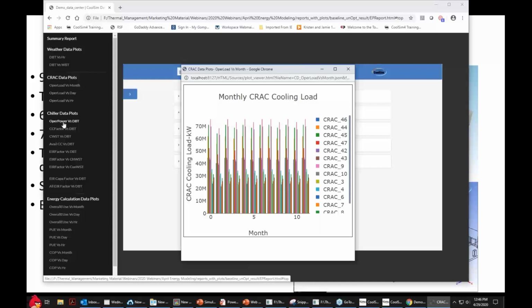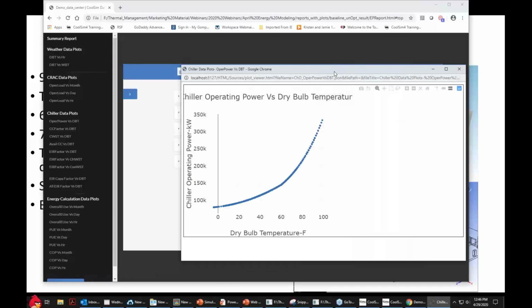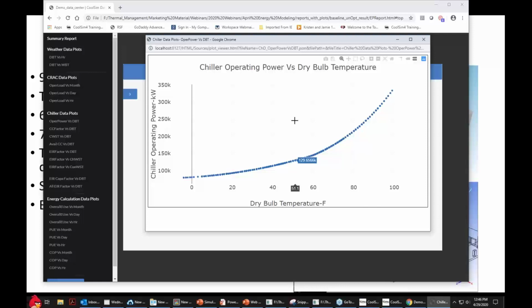You wanted, let's look at operating power versus dry bulb. Yeah, so this is an example of how the chiller's operating power varies as a function of the outdoor dry bulb, and there's 8,760 points plotted on this XY plot. The operating power has several adjustments that are made as a function of outdoor dry bulb. The capacity of the chiller is adjusted as a function of outdoor dry bulb, as well as the power of the chiller. And the part load ratio varies as a function of outdoor temperature as well. So those are all combined in the graph that we see here, which shows that the chiller takes more power as it gets hotter out.